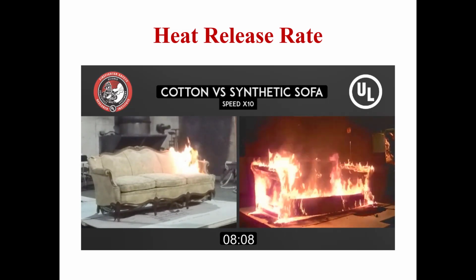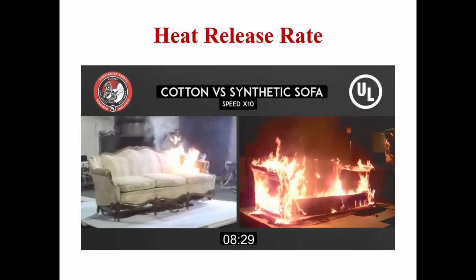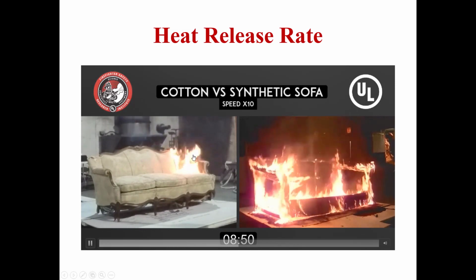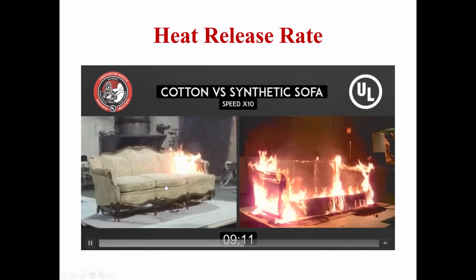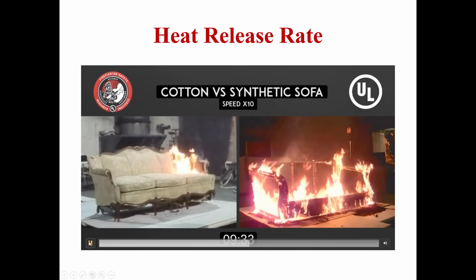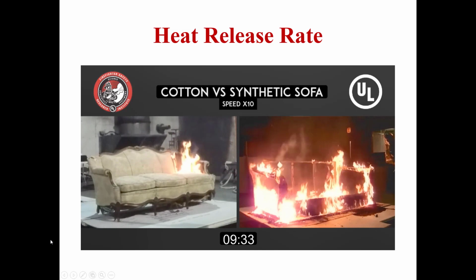This video goes on for a few more minutes. We'll stop it here, but basically this fire on the left does not completely consume the sofa until the 30-minute mark. So we can see the difference in the heat release rate. The heat release, or the heat of combustion, may be very similar between these two sofas, but the heat release rate in the synthetic material was drastically higher than the heat release rate in the natural fiber material.